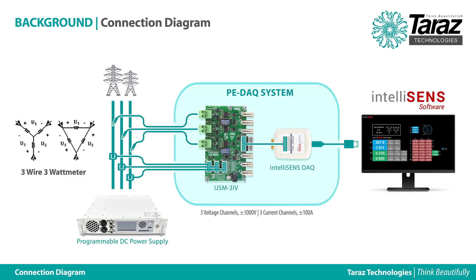The connections are made to measure voltages and currents in a three-wire, three wattmeter configuration. Since measurements are taken on phase currents and line-to-line voltages, a phase shift will exist between voltage and current waveforms.